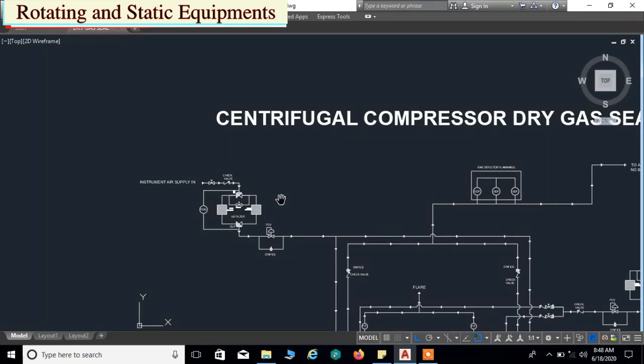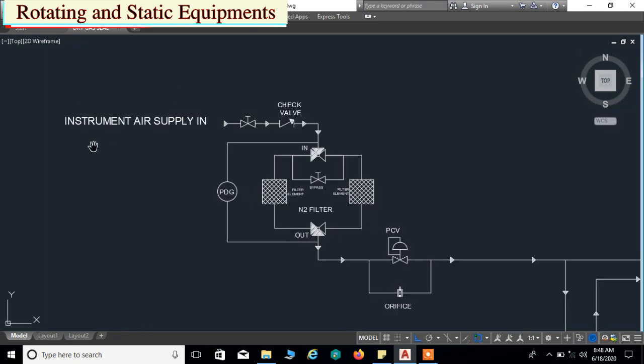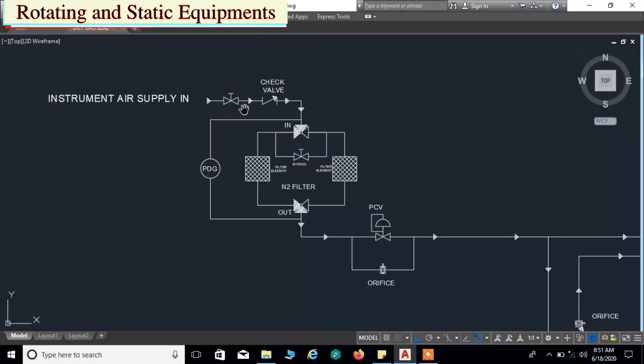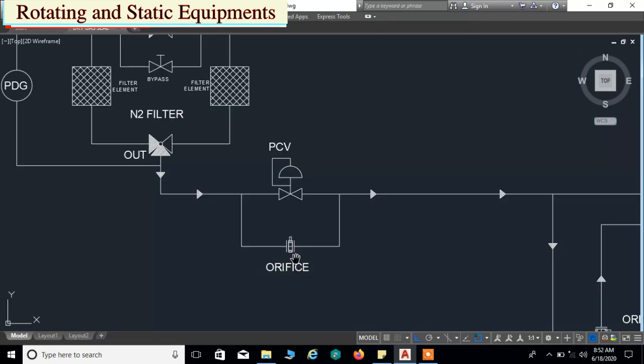Finally we will go to the instrument air supply. The inlet pressure of the instrument air is 8 bar. The instrument air passes through a filter for removal of foreign particles and dust. This is a replaceable cartridge type twin gas filter, piped in a parallel arrangement using a continuous flow transfer valve. Cleaned instrument air is then injected to the tertiary seals through an orifice, and the instrument air pressure is controlled and maintained by a pressure control valve.